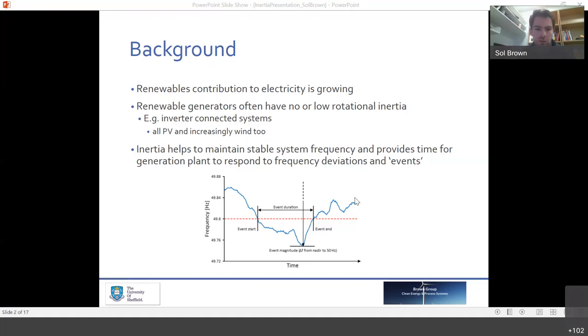Inertia is a property which acts as almost a viscosity, a dampener on the movement of these oscillations. So if you have enough inertia on your system, the excursion out of your frequency domain will be slower, and the amount of frequency response you need to deploy will commensurately be lower. So you have these two things which are tied together: the ability of a system to respond to frequency, and the amount of frequency excursions and the amount of inertia on the network. And this is likely to dominate a discussion about why inertia is useful, because of the lowering amount of inertia as renewables increase on the network.